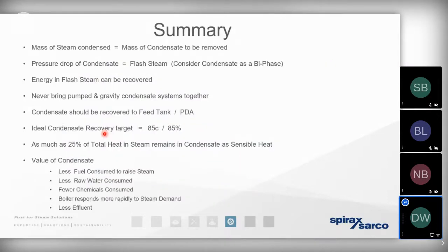So just to summarize, the mass of steam is going to equal the mass of condensate. We want to remember that condensate is a biphase, especially when we've got a pressure drop, and that biphase is going to result in flash steam that is typically vented away to protect a process from expansion or to protect pumps from cavitation. We don't have to lose the energy in that flash steam. We can recover it by passing it across a simple heat exchanger or by condensing it to keep the amount of condensate we can recover to the maximum point. Remember that rule of thumb: 85 degrees, 85% of the condensate. That's a target we should be aiming for, and that will give us an indication when we've got a condensate recovery system that is working efficiently.